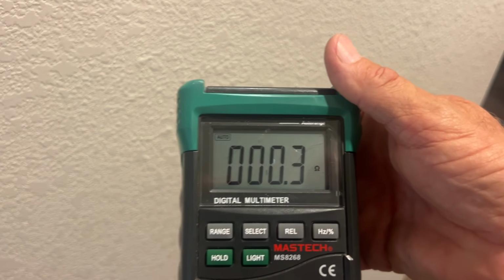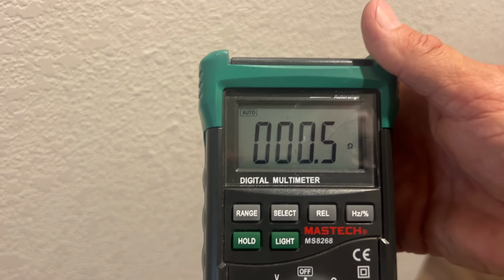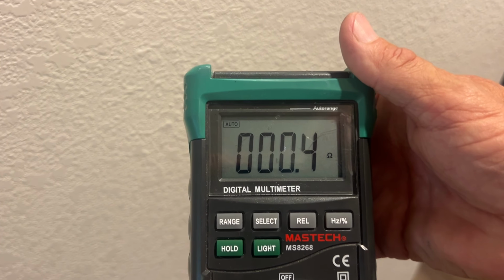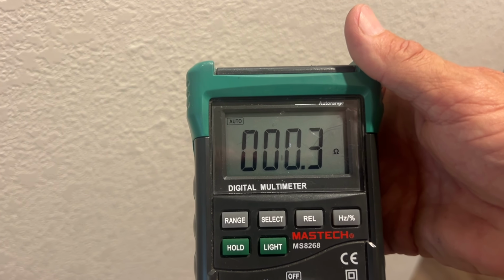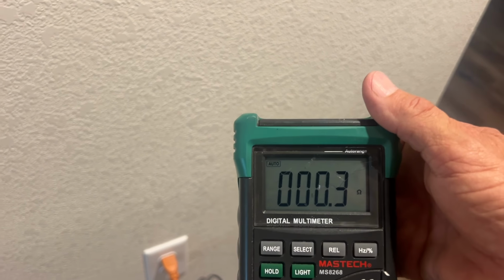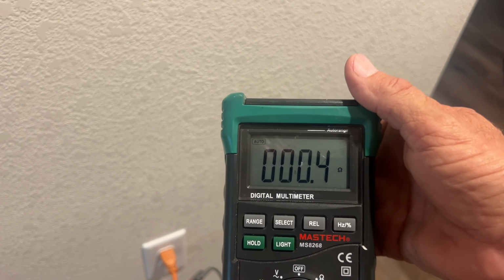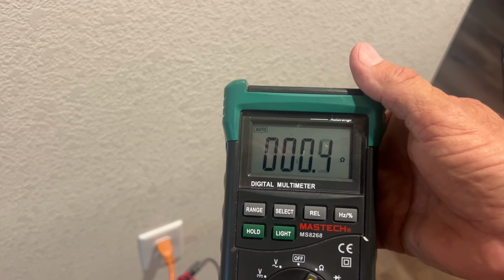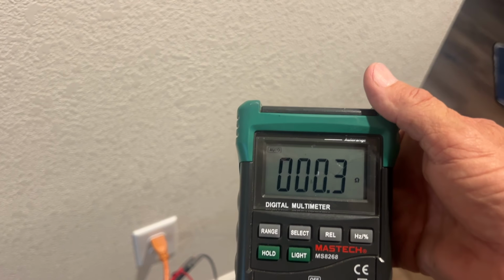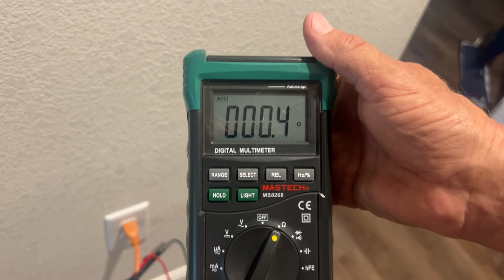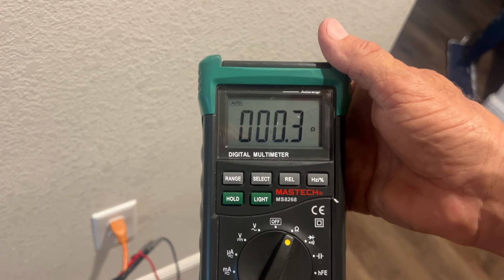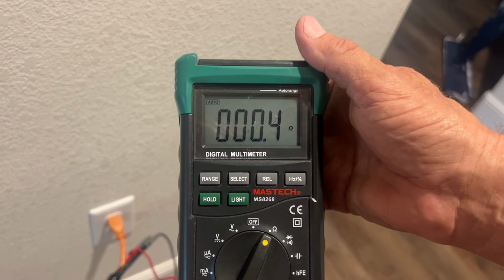1.1. This one we earlier determined is the closest one, the first one on the circuit, and look at that - we've got about 0.4. This one definitely has the lowest resistance, around 0.3 to 0.4, so it's going to be the closest to the breaker panel, the first one on the circuit.